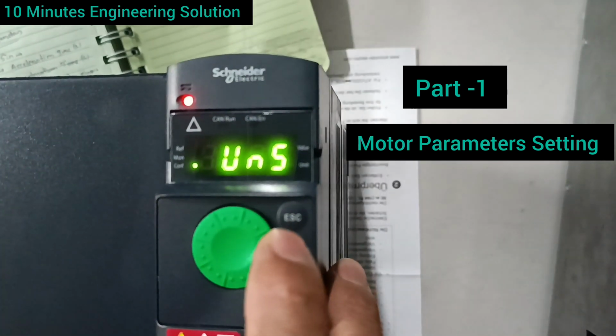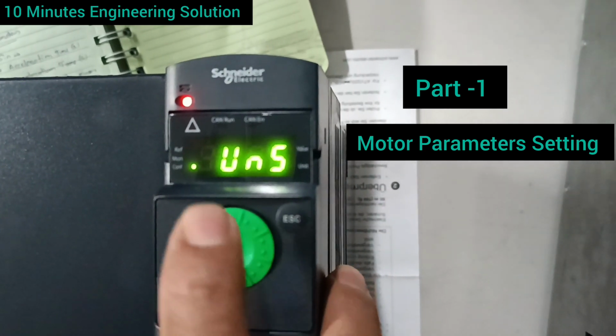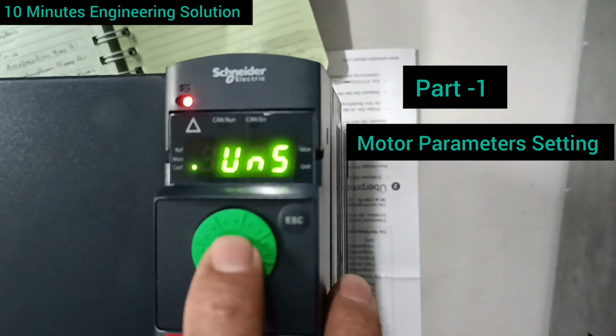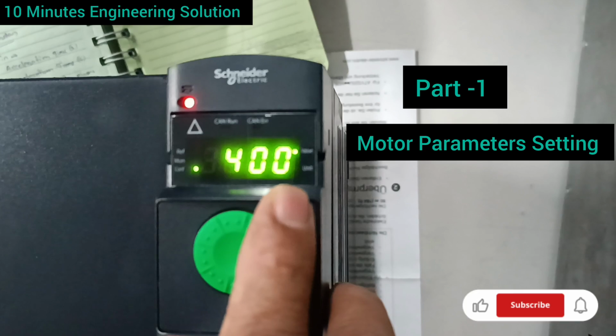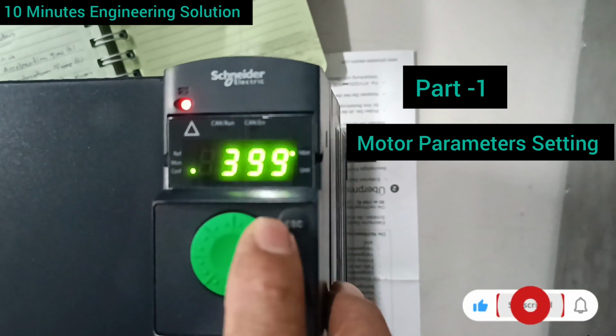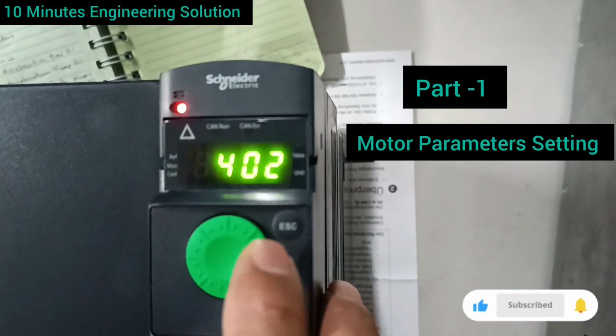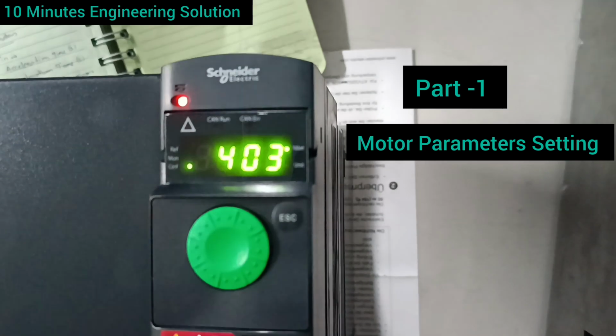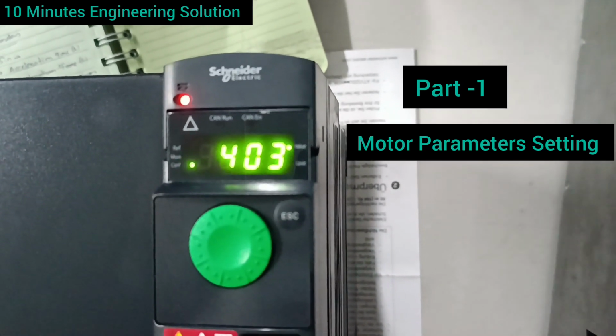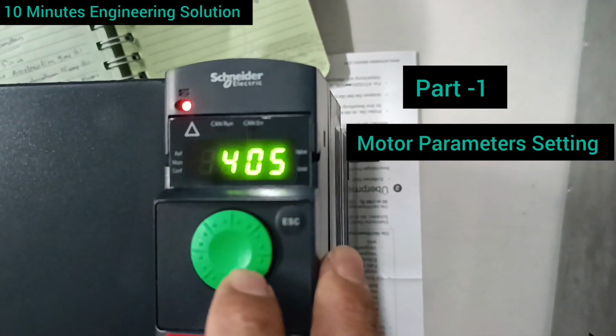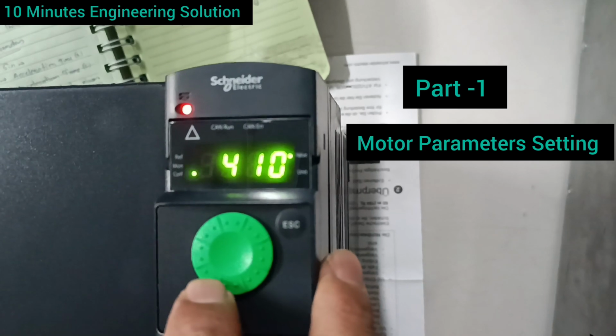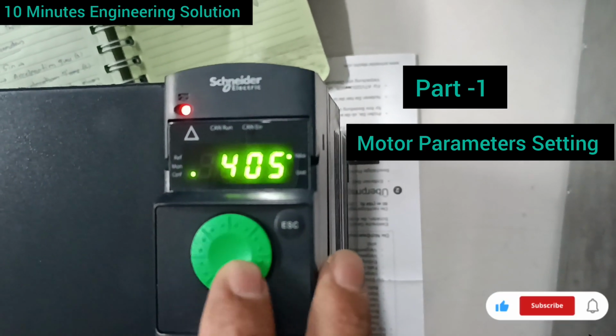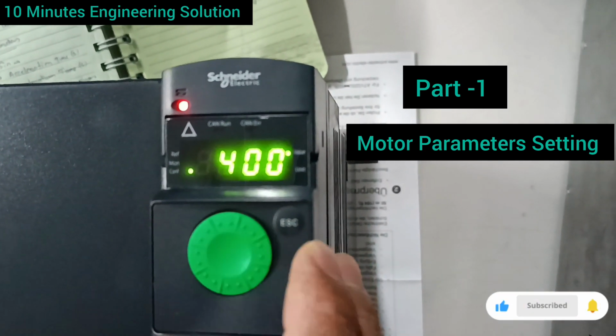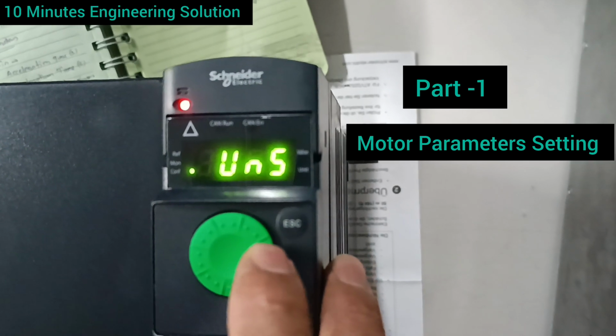Okay, now UNS, rated motor voltage. UNS means rated motor voltage. You can see the picture in here. The motor nameplate value is 400, so I just enter 400 volts. If your system has voltage variations, you can adjust by scrolling this dial. In my system I have 400, so I just set 400 volts.